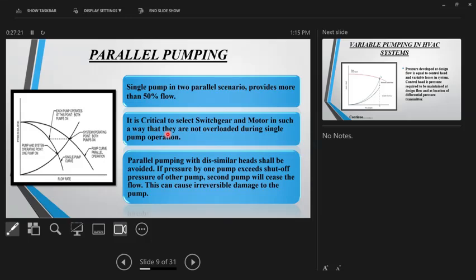The simple reason is you would design the piping system or pipe size for all pumps running, and consider the associated friction drop, etc. But when only one or two pumps are running, practically there is no resistance to the pump, which forces the pump to overflow. So if you have constant speed pumps in multiple numbers, this particular aspect has to be very carefully thought through.